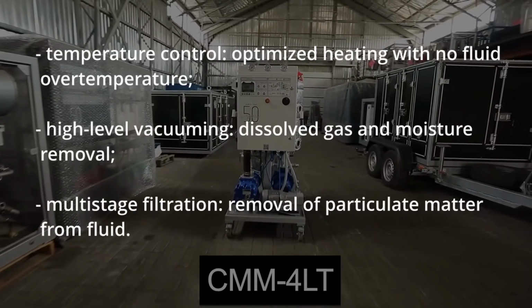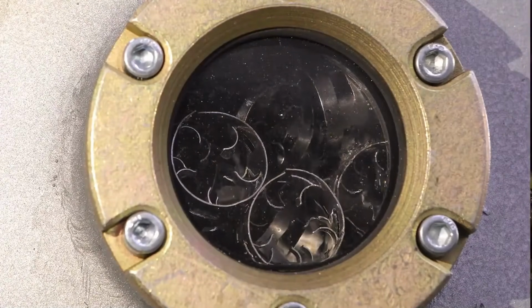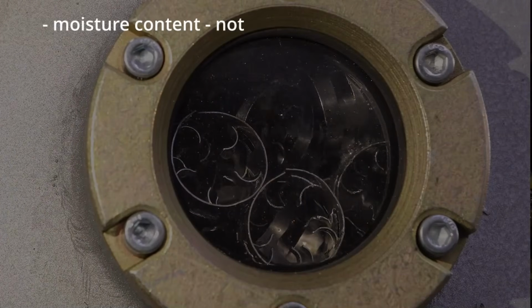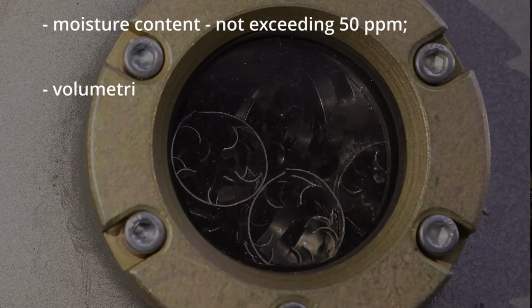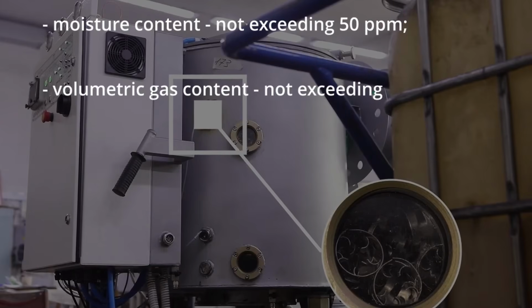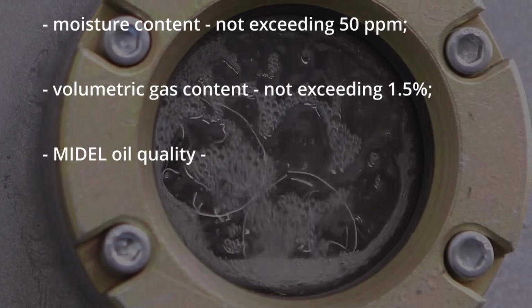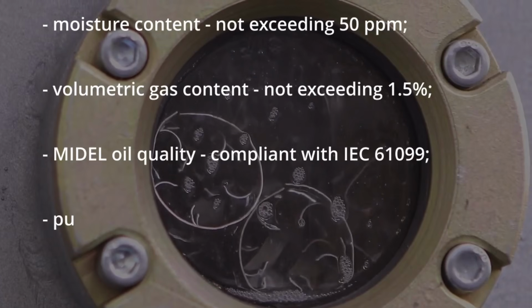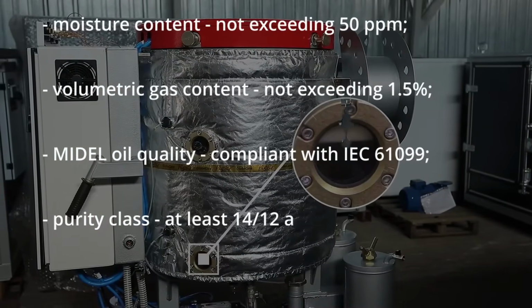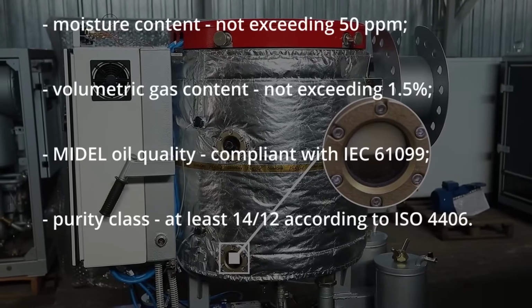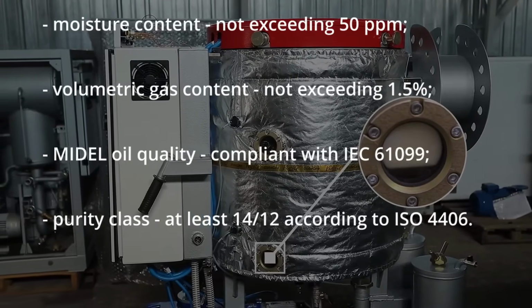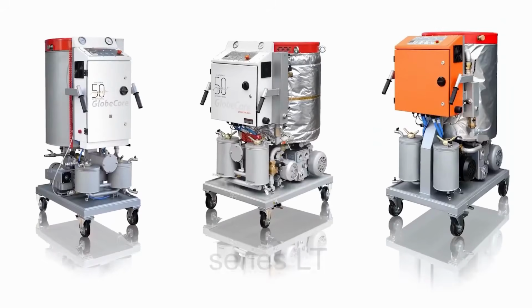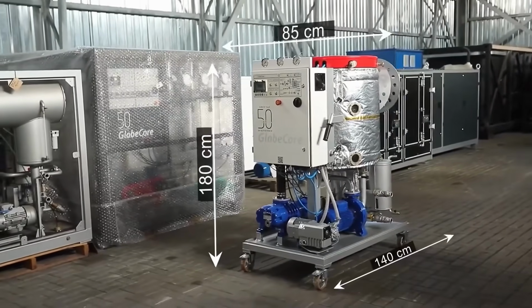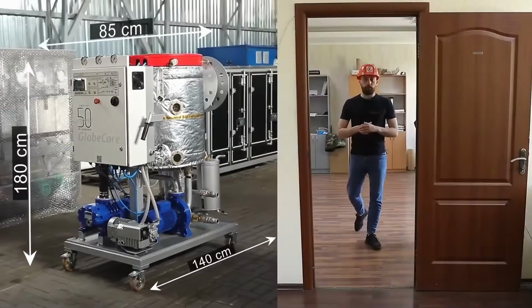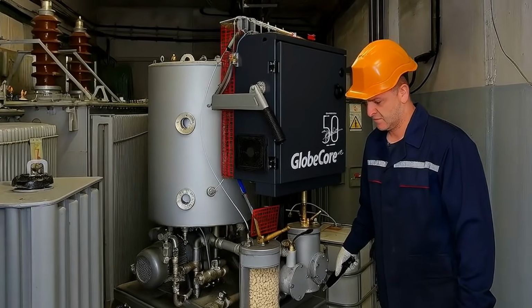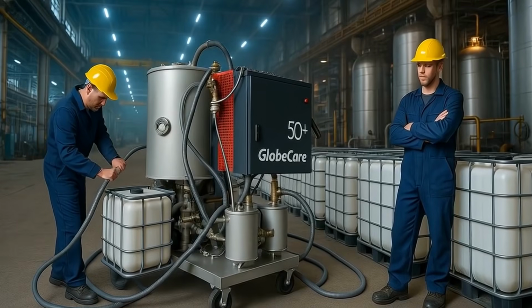Processing results: moisture content, not exceeding 50 parts per million. Volumetric gas content, not exceeding 1.5%. MIDEL oil quality, compliant with IEC 61099. Purity class, at least 14/12 according to ISO 4406. In addition to their technical advantages, the CMM-LT units feature compact dimensions and the ability to be used in confined indoor spaces, including transformer substations or oil storage facilities. They are easy to transport and integrate into the existing production cycles.